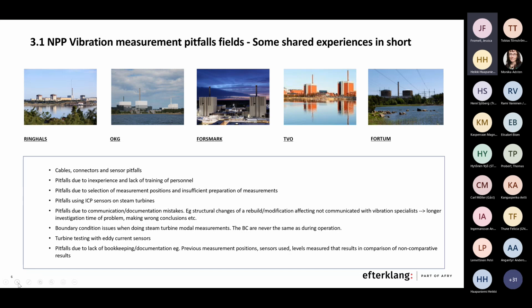And then you also have pitfalls due to communication and documentation mistakes. For example, you have made a structural change or a rebuild in the plant, and this has not been communicated properly to, for example, vibration specialists. This might cause a longer investigation time for a problem, and you make the wrong conclusions. Then boundary condition issues have also come up. For example, when doing modal measurements on steam turbines, the boundary conditions are never the same during operation as during the modal measurements. This might cause, for example, an inexperienced person to draw the wrong conclusions from the measurements, maybe when correlating with calculations such as FEM or CFD.